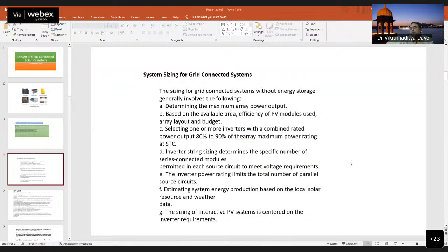आप कह रहे हैं नहीं साहब मुझे पूरी लैंड पे ऑक्यूपाई कर दो, और आपने देखा कि आपका ग्रिड तो अलाउड ही नहीं कर रहा है, क्योंकि हर गवर्नमेंट ने अपने रूल्स रेगुलेशन बना रखे हैं कि जो ट्रांसफॉर्मर मोहल्ले में लगा है, उसके, मैं राजस्थान की बात कर रहा हूं, उसके 80% के लोड तक आप अपना ग्रिड कनेक्टेड लगा सकते हैं। यदि आपके मोहल्ले में 100 केवीए का ट्रांसफॉर्मर लगा हुआ है, तो 100 केवीए का उसका 80% कितना होगा?